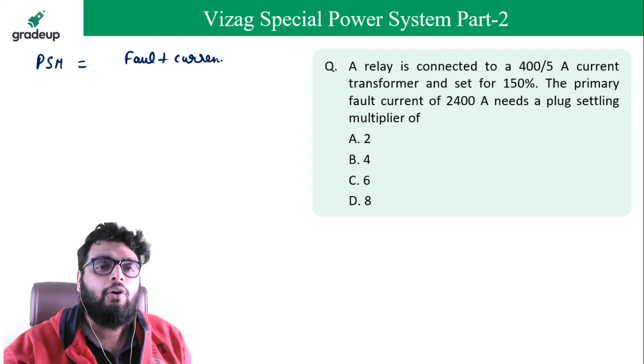Simple question, if you know the formula. A plug setting multiplier is used where? It is used in a relay. Plug setting multiplier is equal to fault current in primary divided by secondary rated current multiplied by current transformer ratio multiplied by current setting. This is the formula, and I am telling you this particular question has been asked many times. Same question, the same language, just they have changed the values or magnitudes.